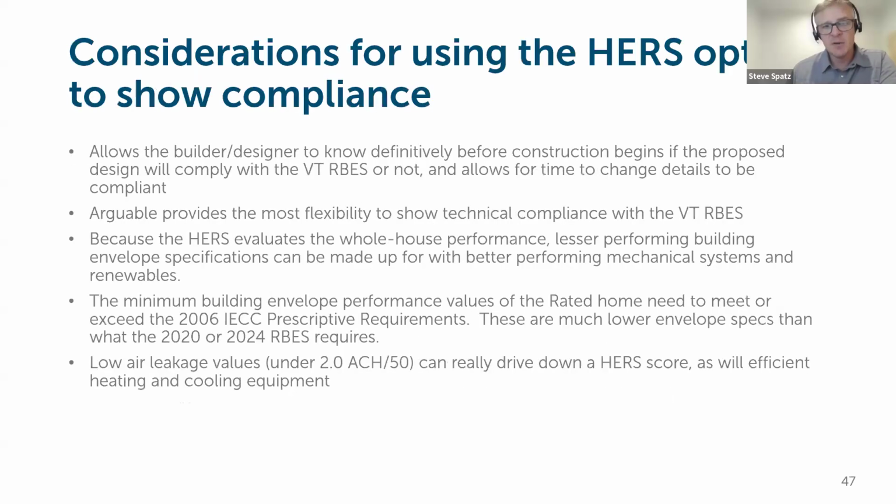So it does give a higher level of oversight to some extent over the actual performance aspects of the building. Again, it takes into account the totality of everything included in the performance of the building, not just the assets of the building shell. That's the big difference between REScheck and HERS: REScheck is only evaluating compliance with the code based on the attributes of the building envelope. It has nothing to do with the airtightness of the building, getting the building tighter than it would be required by code, the performance of the mechanical equipment, et cetera.